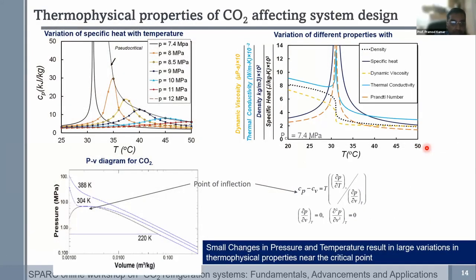There were some questions on the properties, and yes, in terms of properties, carbon dioxide does not exhibit ideal gas behavior. It is a real gas. You see a lot of non-linearities in the variation of all the transport properties closer to the critical point. That means the system has to be very carefully designed, taking into consideration the real gas properties and behavior of carbon dioxide. A lot of these issues are associated with coming closer to the critical point. You find these artifacts of operating in the pseudo-critical region creeping in, and then suddenly you see a significant rise in the compression power that is attributed to a large increase in the specific heat and density closer to the critical point.